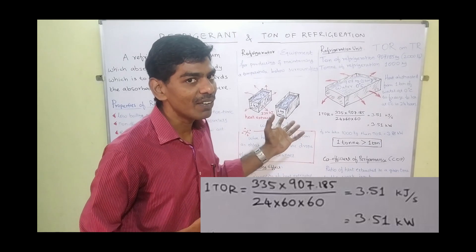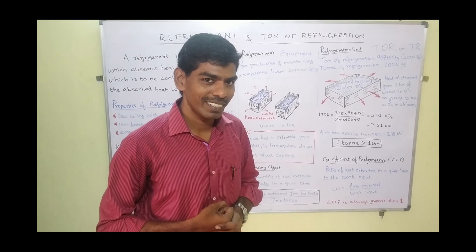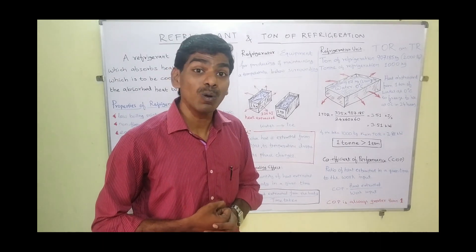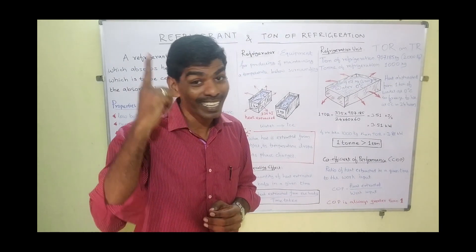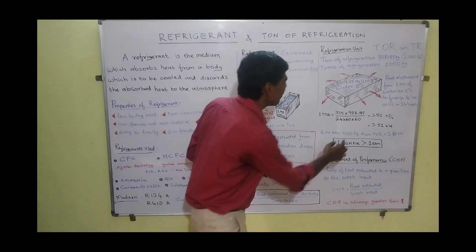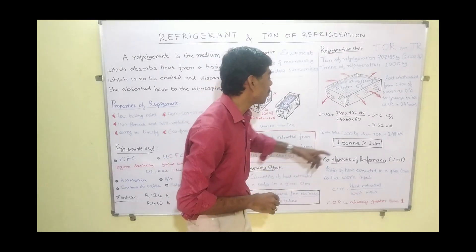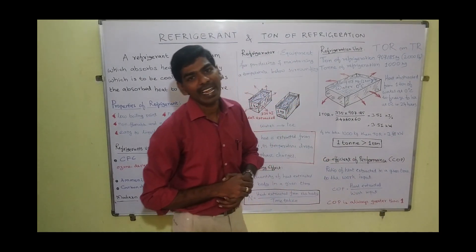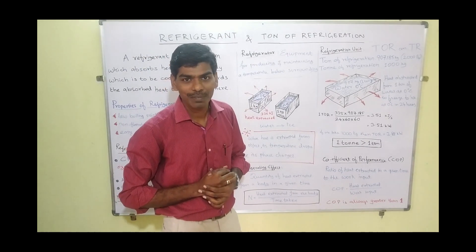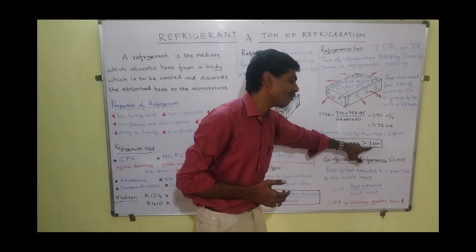If we want to calculate it for 1000 kg of water — that is 1 metric tonne (T-O-N-N-E) — the value changes. Once we replace 907.185 by 1000, we get 3.877, that is approximately 3.88 kilowatt. So what we understand is: 1 metric tonne of refrigeration is greater than 1 short ton of refrigeration.